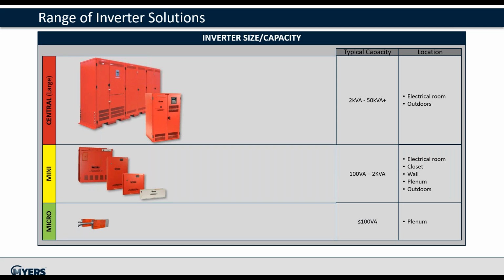The traditional large central systems are used on applications from 2 to 50 kVA, installed in electrical rooms. The mini category from 100 VA to 2 kVA is typically installed in closets, wall-mounted, ceiling grids, and on roof beams. The micro application, less than 100 VA, is typically mounted near the fixture in the ceiling.